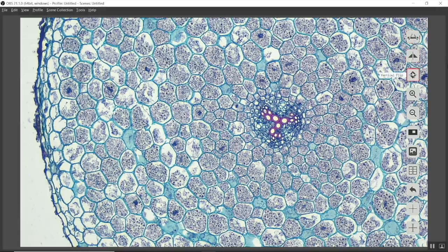You may flip your image horizontally, you may flip it vertically, zoom in, zoom out, create a mask. You just draw a box, and the area of the specimen that you want to show will just be in that box. The rest will be black. Playback accesses the SD card on the camera and allows you to view the images that you've captured. You may compare images as well. You can undo something or cancel an operation. And then there are cross line and ruler options to place over the image.